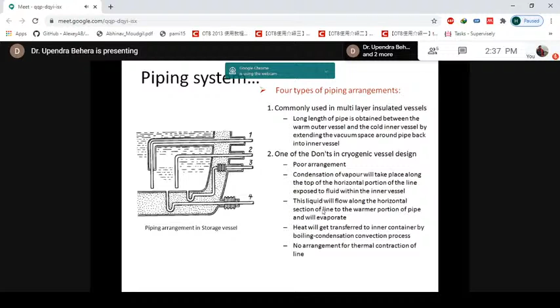And the third one, if you see here, they have used the bellows for thermal contraction, and vertical rises in the vacuum space are used, because this can take care of the percolation of the liquid, which we'll see in the next arrangement. In the third arrangement it is like that, but they have put the expansion bellows inside the insulation space, or the vacuum space, where a leak may occur because these are all thin-walled bellows, and the leak may occur because of fatigue failure, because of continuous cooling and heating of the container. When we are putting in cold, it gets cooled, and when it comes to room temperature and again cools down to cryogenic temperature, or the cryogens are being transferred or it comes to room temperature and is refilled, that time fatigue may occur, and it is difficult to maintain, and also it is a very costly affair to repair that.